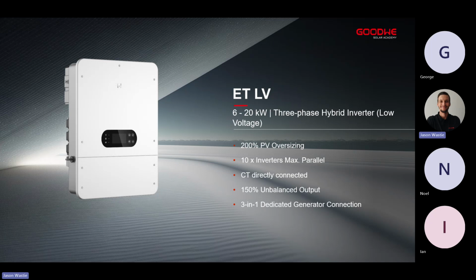Next is CT directly connected. So if we look at CT directly connected, this means that we do not need a physical external energy meter or smart meter. The energy meter is built into the inverter. So we get all of our voltage reference through the energy meter inside the inverter, and we connect a CT or three CTs to the inverter directly, and that is where we get our current readings from. So we don't need to physically install an energy meter externally. We install only CTs, or clamp-on CTs that come included with the inverter.